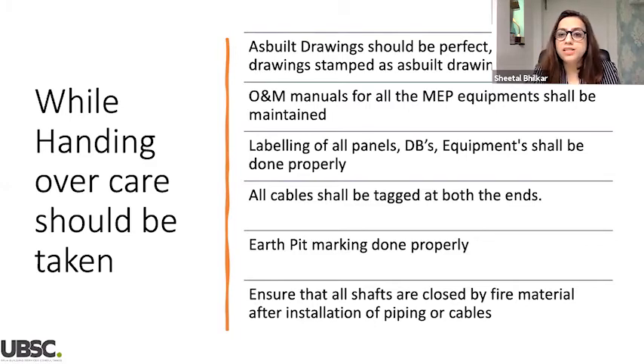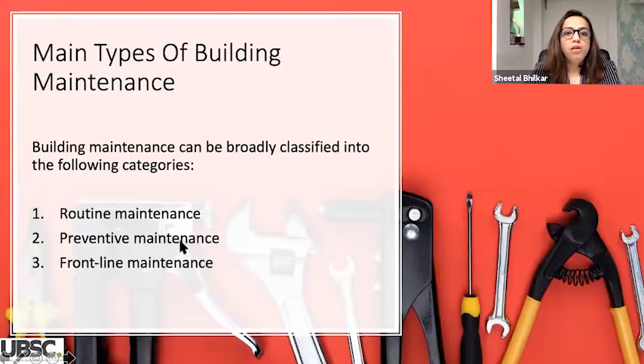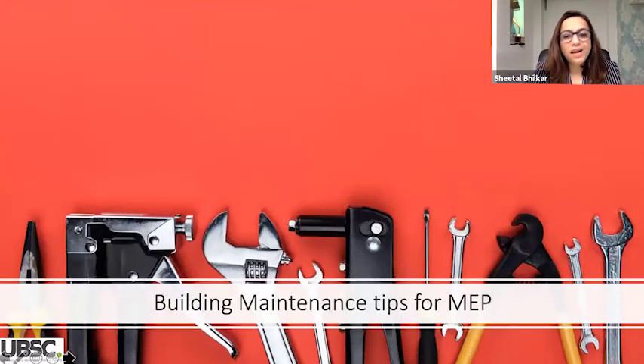Labeling of all panels, DBs, and equipment shall be done properly. All cables shall be tagged at both ends. Pit marking should be done properly, and you have to ensure that all shafts are closed by fire material after installation of piping or cables. This should be taken care of. So I'm not going to talk much about maintenance, because my other panelist is going to talk about maintenance, but yeah, these are the 3 types of maintenance, and I'll surely give a few tips about maintenance of MEP.